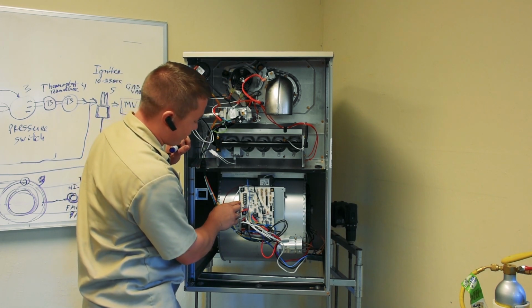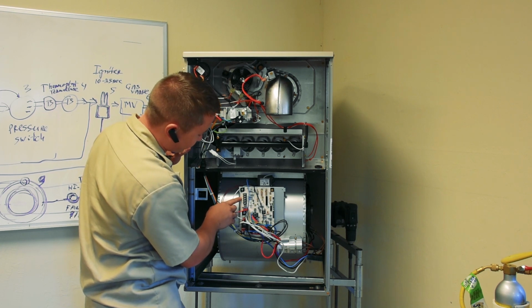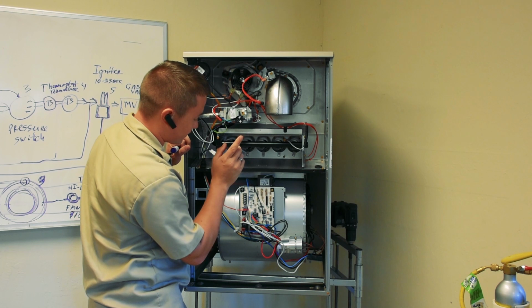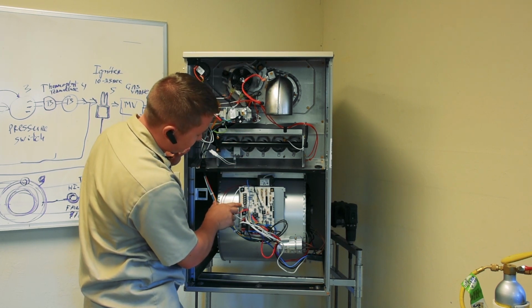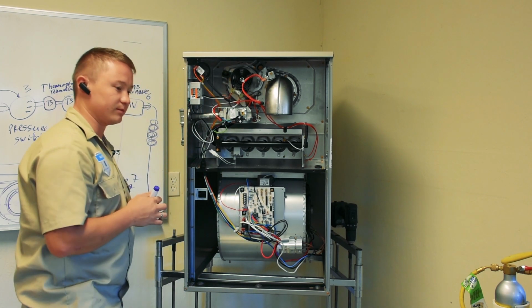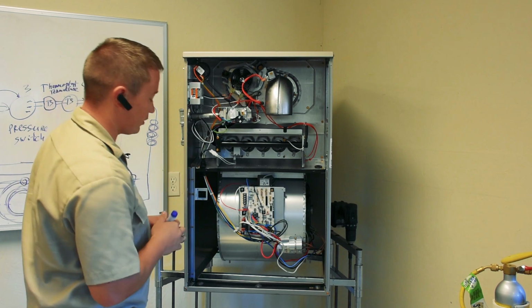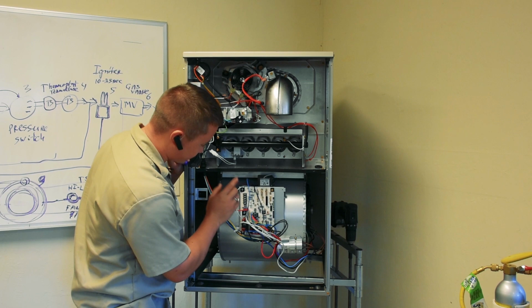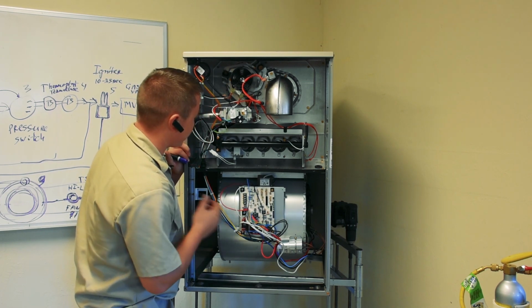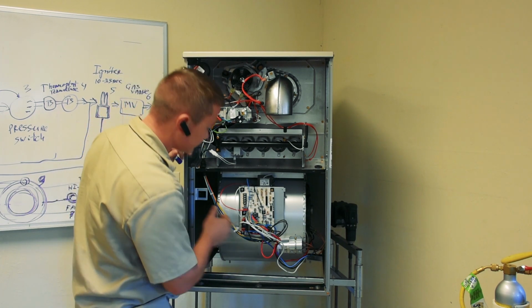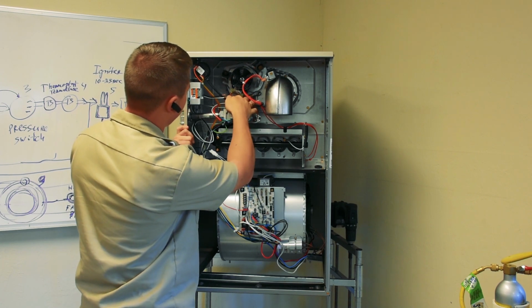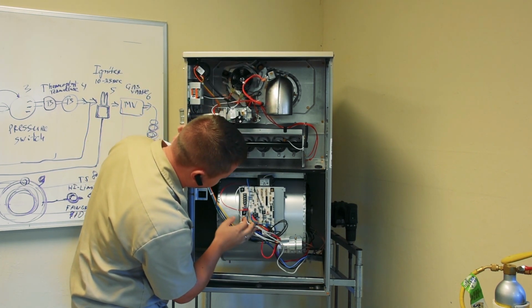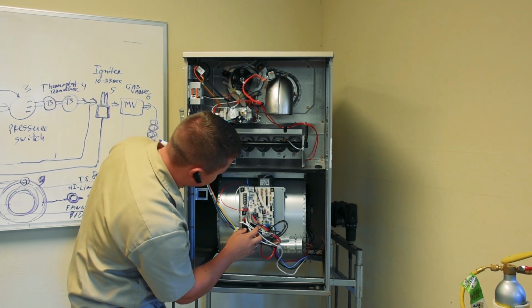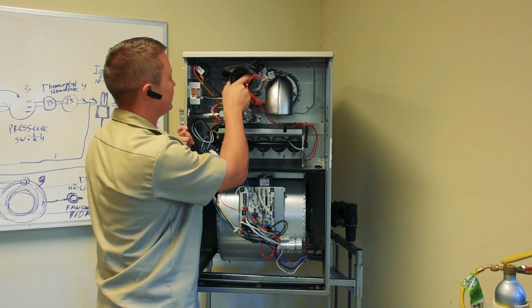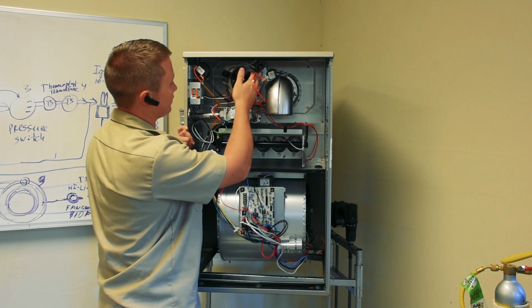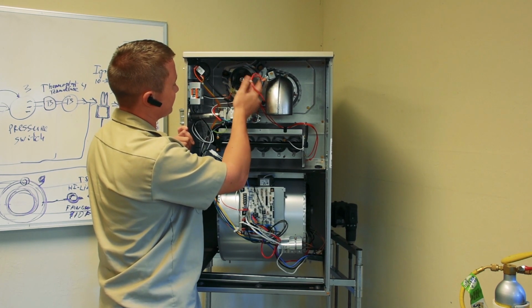When you turn on the power on your wall thermostat, you will energize the relay on the thermostat which connects W and R. When you want to make heat, like warm your house, you're actually bypassing W and R. What happens next: here I have a relay connected to the control board, and this is energizing the relay which sends power to the inducer blower wheel motor, and this motor starts running like that.